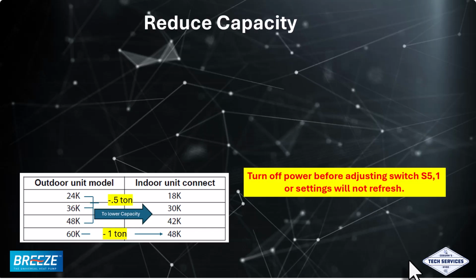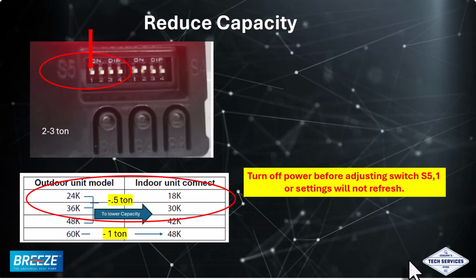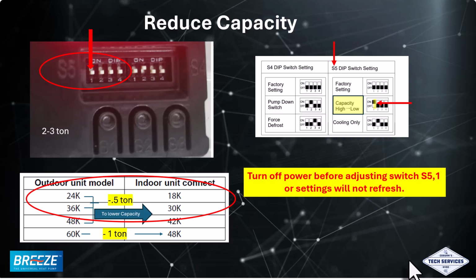Setup is pretty easy also. To reduce the capacity of the unit, you will first turn off the power before adjusting the switch, and we'll go to dip switch bank 5, switch 1, and we'll turn that switch to on position. That will reduce the unit by 1/2 a ton.